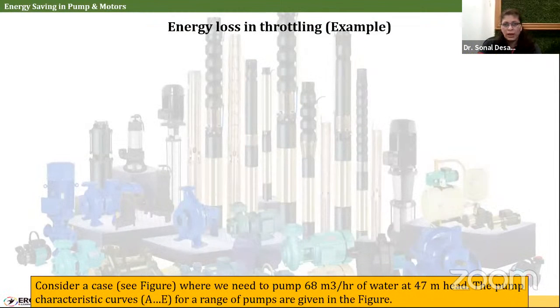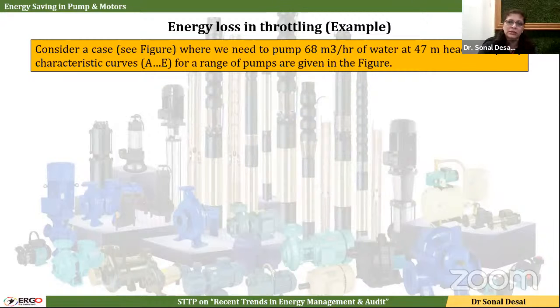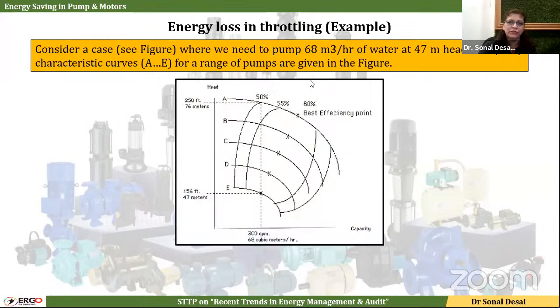If we talk of a numerical or a case study of how flow throttling is affecting, we can see from this diagram that a case is given where we need a pump to handle 68 cubic meter per hour and we require 47 meter of head. So we can select pump A, B, C, D or E out of all available options. If we go with pump E, its operating curve is this, and it will have the best operating efficiency over here. If we select pump A, then it will operate at 50%. Again, it will give us 68 cubic meter of flow, but it will give us more head. And hence, because it is giving more head, it is operating at a lower efficiency.